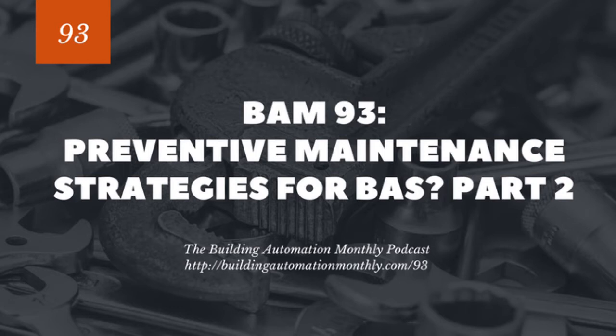So the first thing we're going to talk about is maintaining set points. And this is both a preventative maintenance practice as well as a project closeout slash owner taking possession of a building process as well. Whenever you close out a project or you take possession of a building, you really want to log the set points. Now, on some systems, that's as simple as doing a backup of the system, and that'll be just fine.